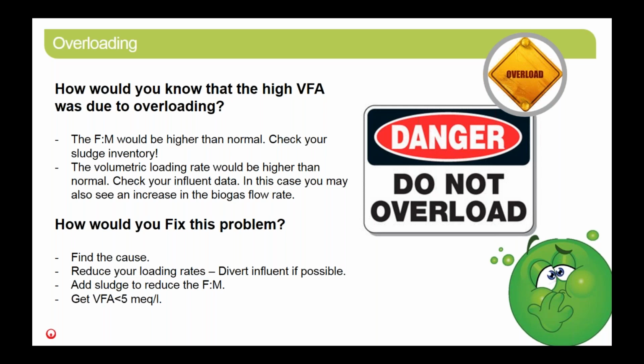If you've lost sludge, you want to add more sludge. If you have a sludge tank available and you have excess, if you carry extra sludge in there, do that. And you don't want to make any increase in loadings until you get the VFA in the effluent down to below 5 milliequivalents per liter.